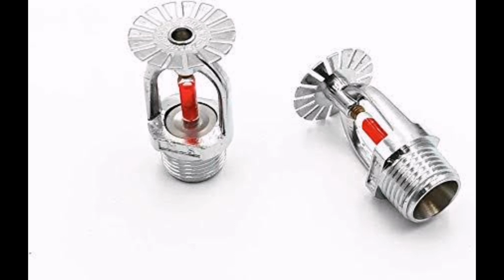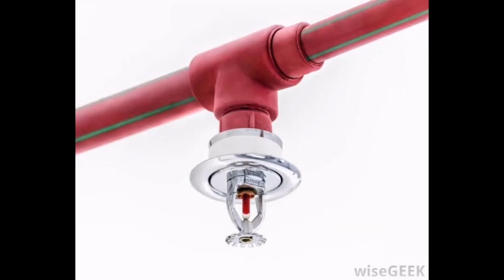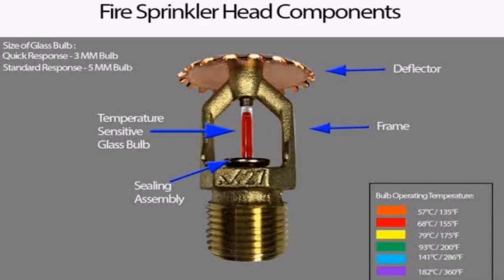One of the most important components of a fire protection system is the automatic fire sprinklers. In general, a sprinkler is activated by the heat put off by the fire once it reaches a certain temperature at the ceiling around that particular head.